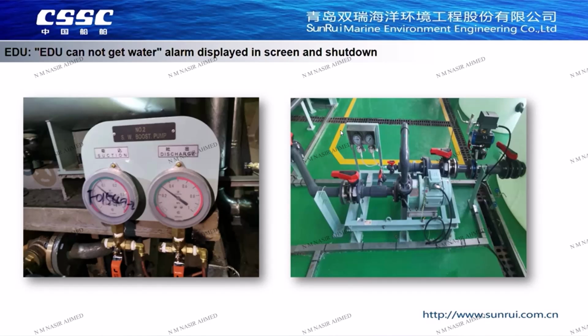Next, observe whether the pressure gauge of the dosing pump fluctuates and whether pump pressure can be established, same as the booster pump. Sometimes, pumps cannot pump water because of the air contained in the pipeline. It is necessary to deflate the air in the pipe if the system is not operating for a long time, especially the booster line.